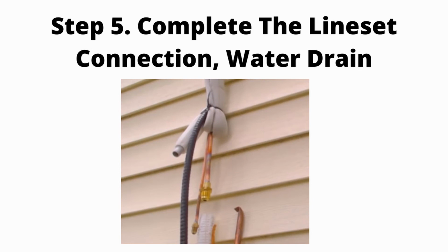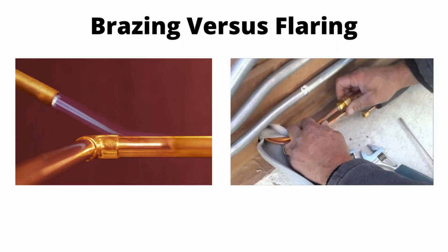The fifth step is to complete the line set connection, water drain connection, and electrical wiring from the indoor to the outdoor unit. As a contractor, we braze all of the connections to prevent leaking of the refrigerant. Since brazing is an advanced skill that takes about 6 months to learn, not all contractors braze their line sets. Many contractors use a flare nut to connect the copper. This is acceptable, but the refrigerant will leak out over time, and every few years you will need to recharge the refrigerant, which can become expensive over time.